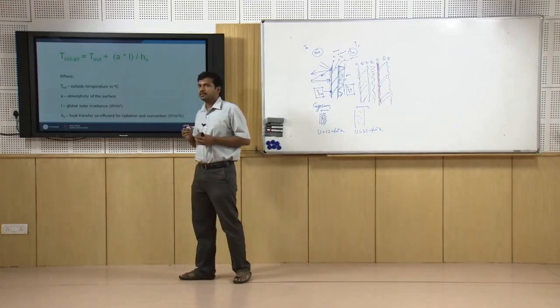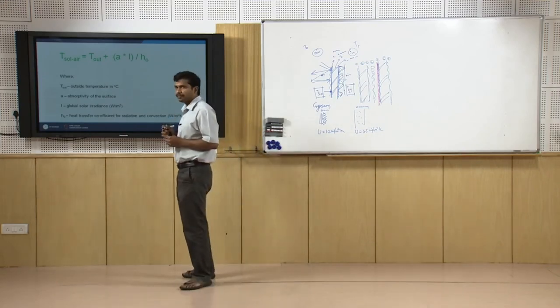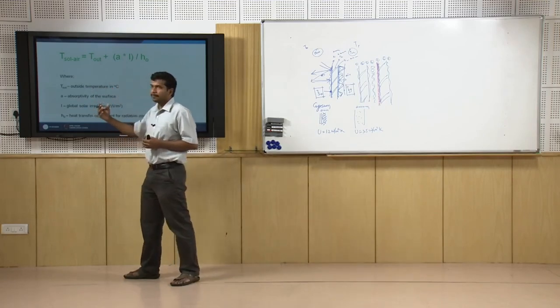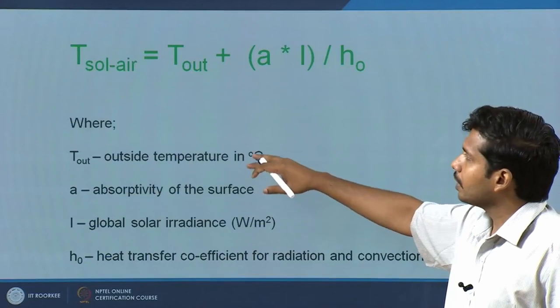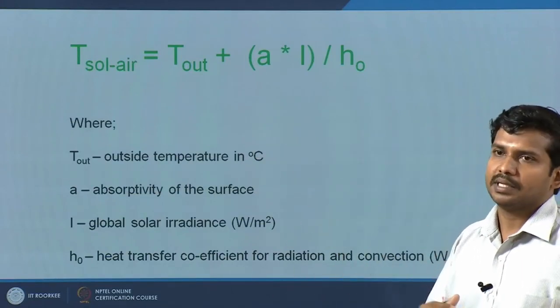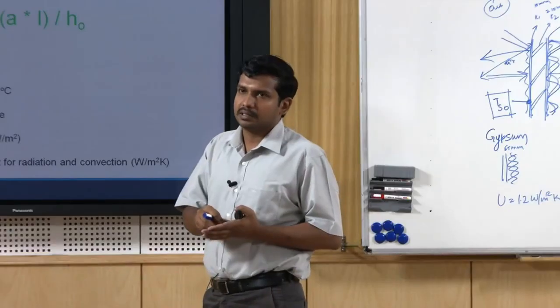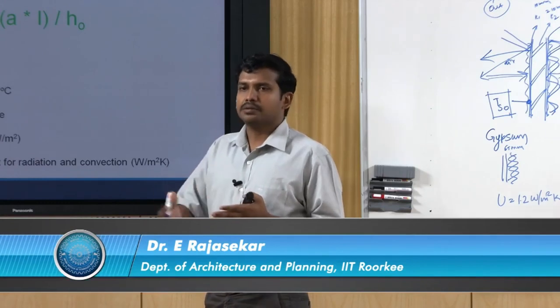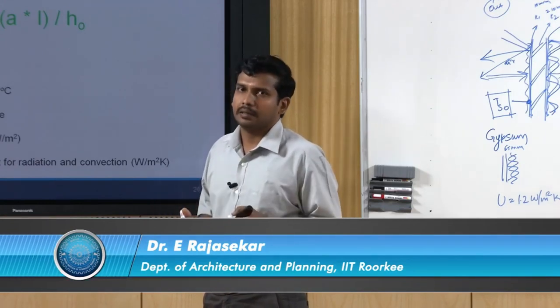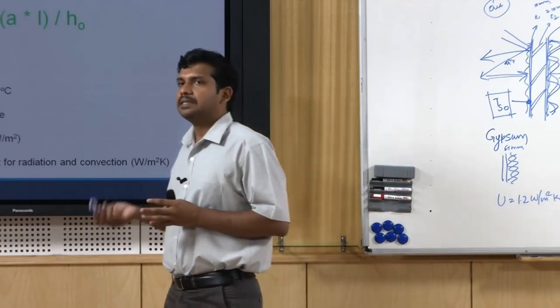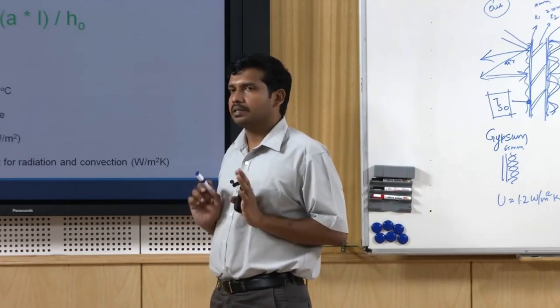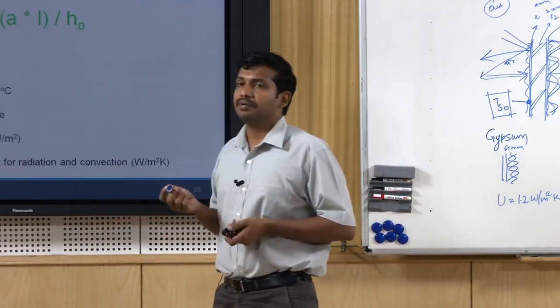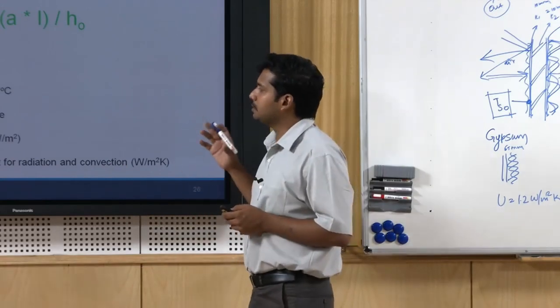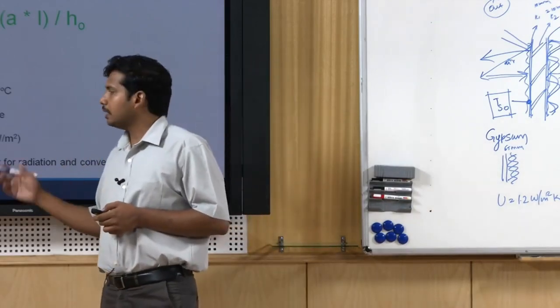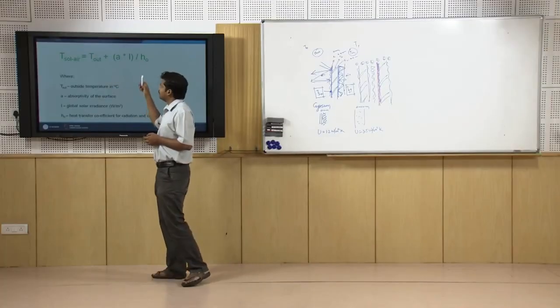The ambient temperature, say in summer in a hot dry climate, may go up to 45 degrees centigrade. But there is a concept called Sol-air temperature, where you have to add the effect of ambient air temperature along with the incident solar radiation falling on a surface. Naturally, when the sun falls, the short wave radiation falling on a surface also increases the surface temperature through radiative heat gain. So, the surface gets pretty hot. When the ambient temperature is 45 degrees, on a typically grey or even white surfaced wall, the surface temperature on an east or south facing wall during summer is bound to go as high as 55 to 58 degrees centigrade. It varies considerably based on the surface property, the solar irradiance, and the third is the heat transfer coefficient. So, this particular equation is really important.